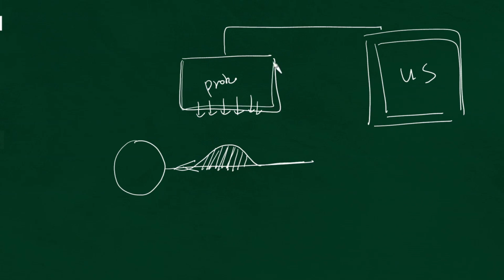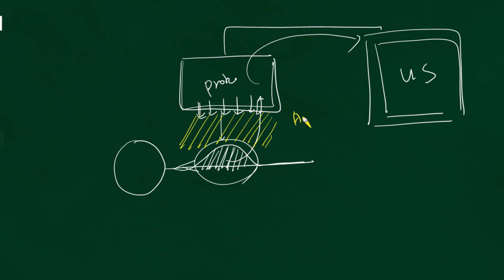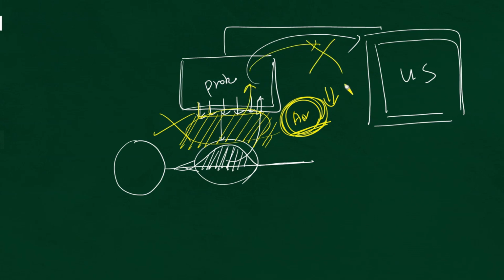Then, you need to transmit the ultrasound to the abdomen using the probe. After sending the signal like this, the returning signals are collected and used to create the ultrasound image. But the problem is that there is air between the probe and the abdomen. What exactly is this air? It has a very low acoustic impedance value. So when the ultrasound encounters air, it doesn't transmit well and just disappears. That's because air hardly reacts at all. So when the sound waves you send hit the air, they all just disappear. When this happens, there are no returning signals, so you can't create an ultrasound image.